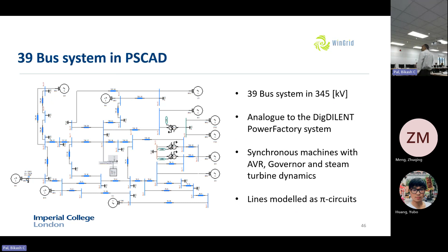Now, that was for the STATCOM alone. Next we put the STATCOM, wind farm, and synchronous machines all in a network—a 10 machine, 39 bus system. We have both phasor versions and PSCAD versions with synchronous machines including AVR, etc. Then we do EMT simulation in PSCAD and find the response, and compare with the phasor approach, to make sure that whatever modules we've built have correct models.